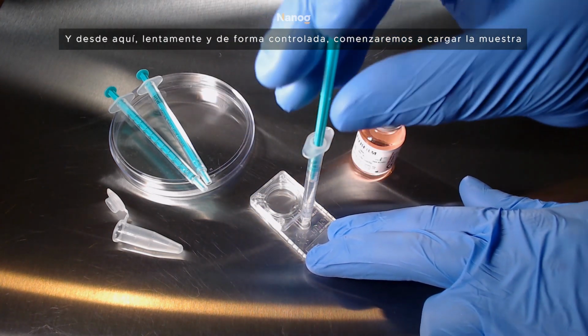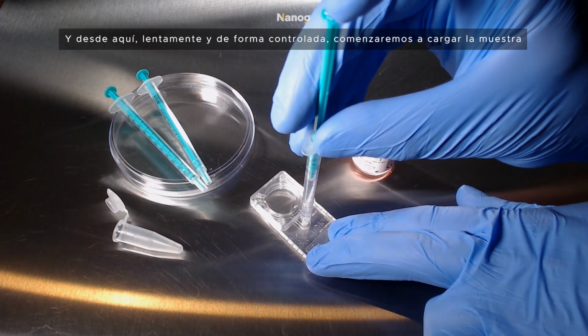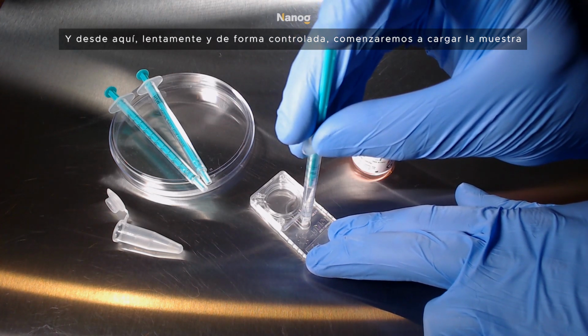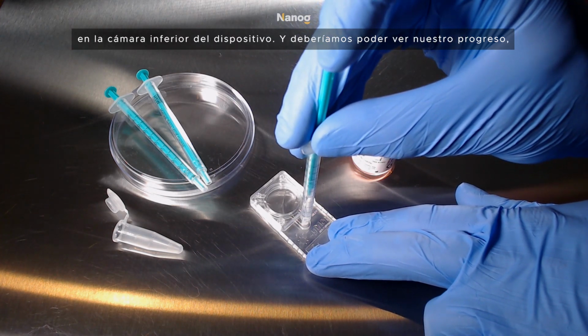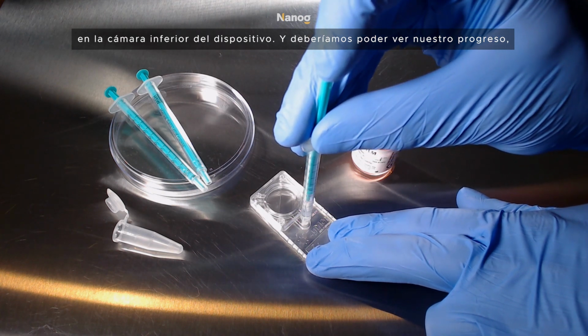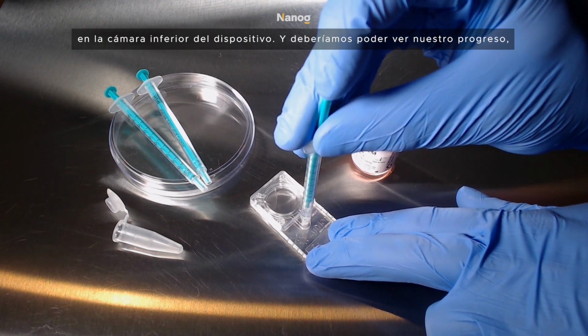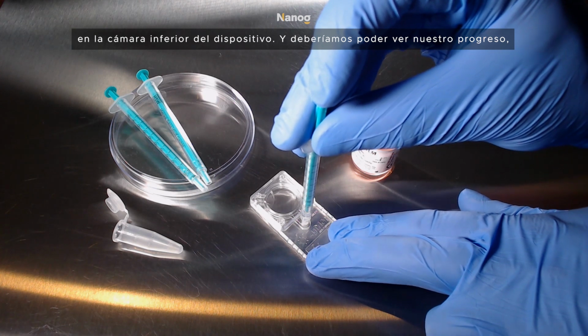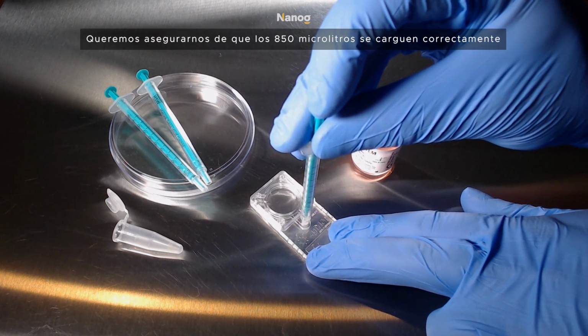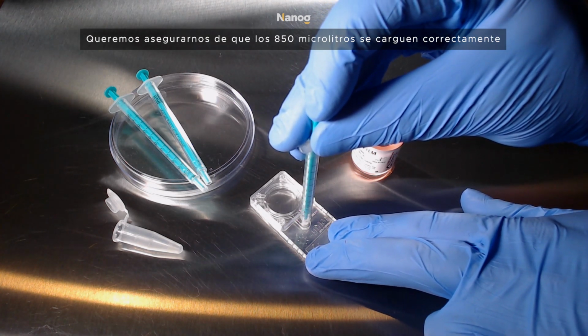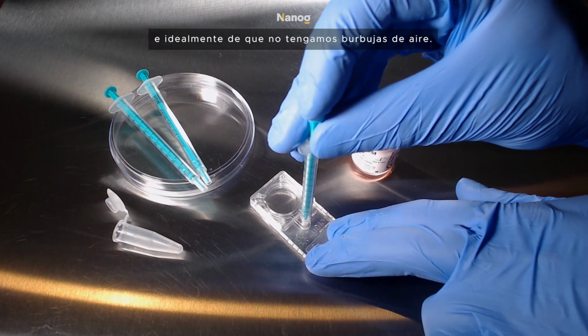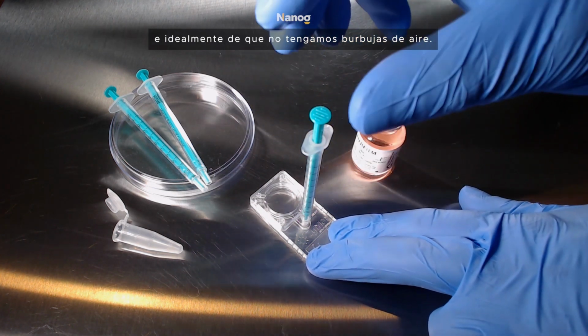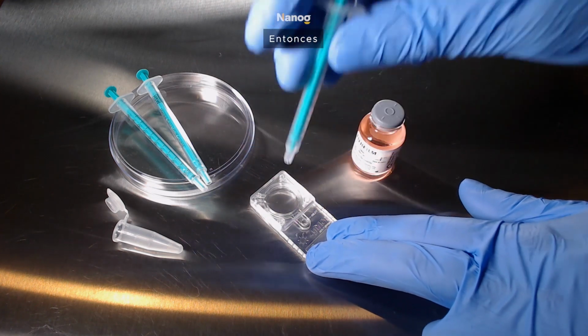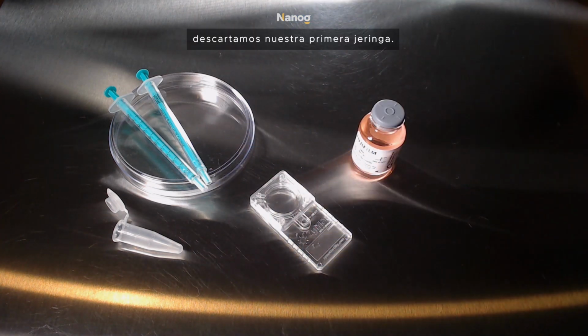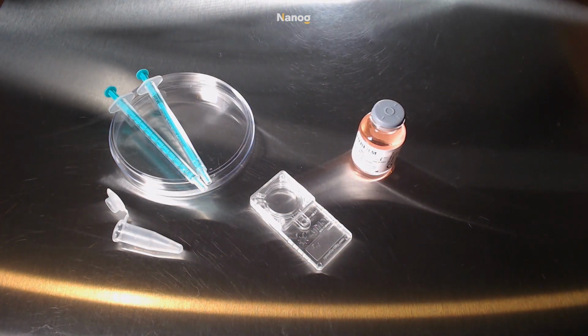And from here, slowly and in a controlled fashion, we will begin loading the sample into the lower chamber of the device, and we should be able to see our progress here. We do want to ensure all 850 microliters are successfully loaded, and ideally that we have no air bubbles. We will then discard our first syringe.